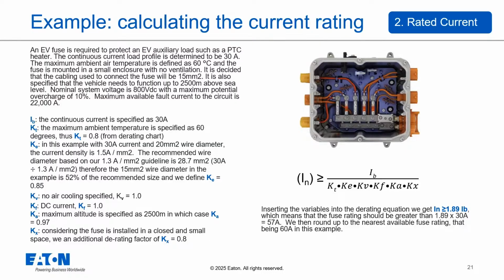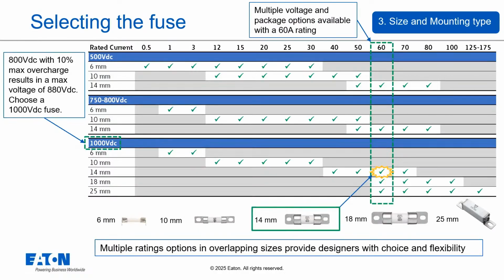Now that we have our voltage and current requirements, we can select the fuse. First, the voltage. The system is 800 volts DC with a potential 10% overcharge, meaning the max voltage could reach 880 volts DC. Therefore, we need to choose a fuse rated for at least 880 volts DC. A 1000 volt fuse is the appropriate choice. Next, the current. Our derating calculation indicated we need a fuse rated at 57 amps or higher, so we selected a 60 amp rating.